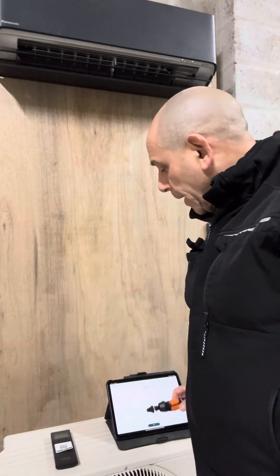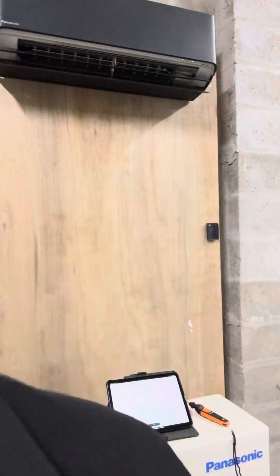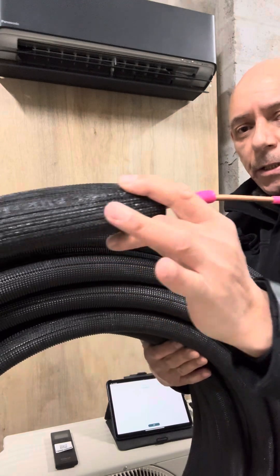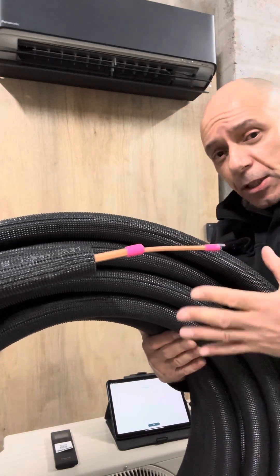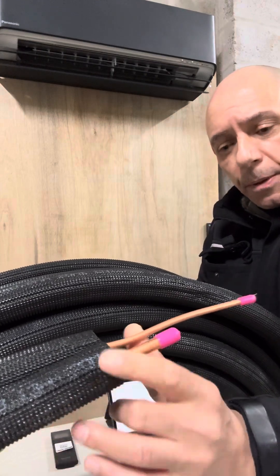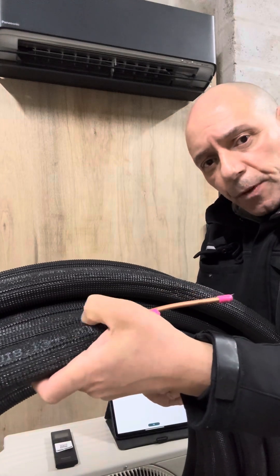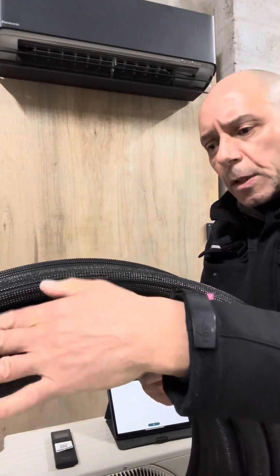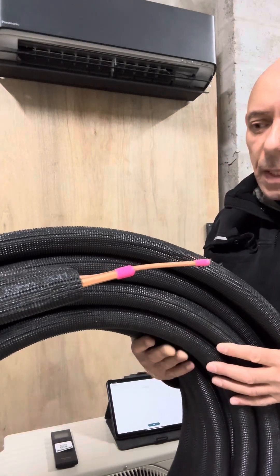For installation, it's relatively easy. What we have is this just comes in a coil — this is a 20 metre coil. Basically it's dual pipe: quarter inch and three-eighths refrigerant pipe. This is fire retardant to an extent — pre-insulated pipes. Everything there is what you need. This will connect from the outside unit to the indoors very easily.